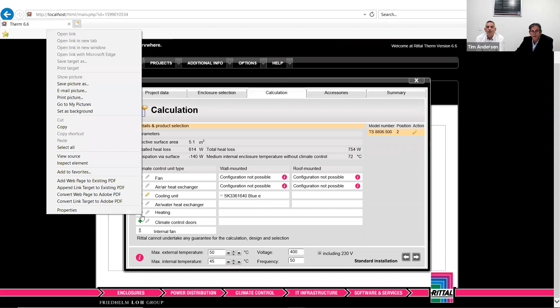Now I just want to come back to the calculation and cover the heating, okay? Because you'd wonder why on earth we'd care about heating. Now, I mentioned early on, we don't worry about latent heat because we regard this system to be a sealed enclosure - moisture doesn't incorporate itself into our calculations, but we still have to worry about condensation on cold mornings. I know of an example with speed cameras where they produce a lot of heat when they're snapping away, but on a cold morning the inside of the camera enclosure will condensate and could cause all sorts of damage. Anyway, carrying on, we've got a minimum external temperature represented here as 5, and we don't really want to go plus 10 degrees in the morning to avoid condensation and whatnot.